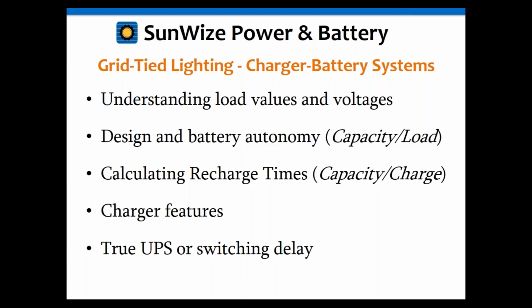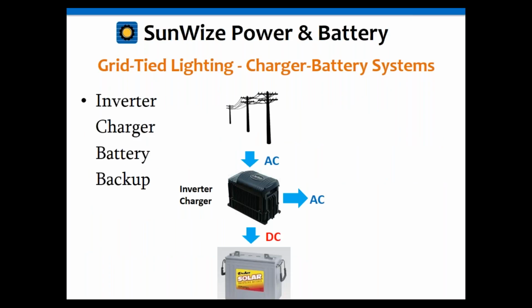The only thing a little different here is that you might want to understand your recharge times with these systems, and then also the charger features, and whether it's a true UPS or switching. If you have ones with a transfer switch in them, there's a switching delay on those, and those may or may not be a problem, and I will talk about that a little bit more in detail. So basically you're going to have that switching delay with an inverter charger type of setup, and basically this is going to mostly apply to AC loads, because obviously a DC load is going to be connected directly to the battery.